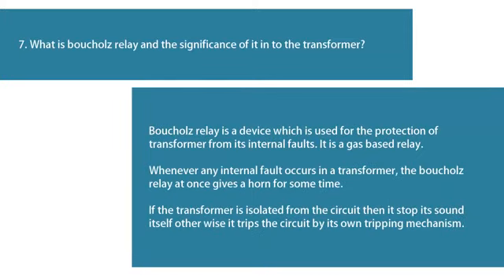Question 7: What is the Buchholz relay and its significance in a transformer? The Buchholz relay is a device used for the protection of a transformer from its internal faults. It is a gas-based relay. Whenever any internal fault occurs in a transformer, the Buchholz relay at once gives a horn for some time. If the transformer is isolated from the circuit, it stops its sound; otherwise it trips the circuit by its own tripping mechanism.